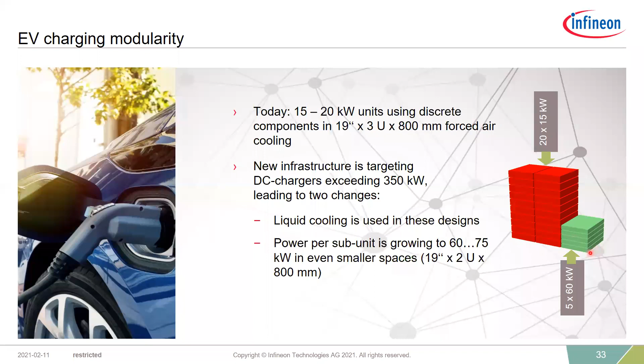But the question is how you can reach this target level. Of course, by choosing an appropriate topology you can improve efficiency, but beyond some extent you need to go for silicon carbide components. By using silicon carbide, you can also switch at higher speed and reduce the overall magnetics, by which you can shrink the size of the racks. On the other front, even switching at higher frequency, silicon carbide chipset losses will be on the lower side compared to silicon IGBTs. So this clearly tells us silicon carbide will be the future, mainly in the direction of electric vehicle charging.